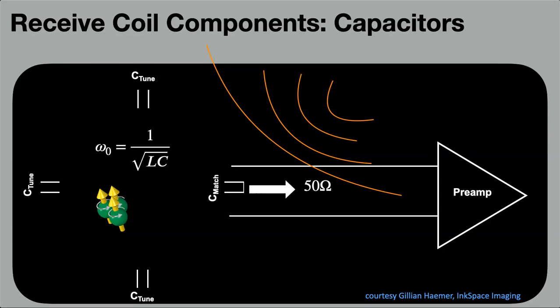So there's another transmit coil. If that was a transmit and receive coil, then you just transmit and switch into receive mode, so that's not a problem. But because this is a receive-only coil, and you've got another transmitter, you have to somehow detune this coil when the other one is transmitting.